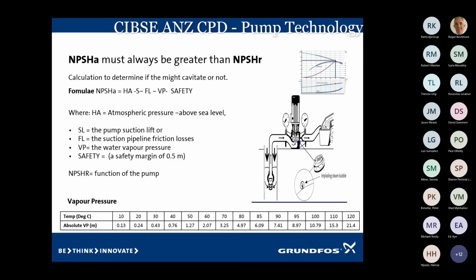We have to take off the friction loss from the foot valve and the pipework. Then we also have to take off the vapor pressure, and the vapor pressure chart is down the bottom there. For 20-degree water, it's not a lot, it's about 0.24. So we take that calculation, and that gives us the net positive suction head available at the pump. As long as your calculation of your net positive suction head available is greater than the net positive suction head required, which is 3 meters, then that pump will work. If you don't have that, then it won't work. It'll cavitate.